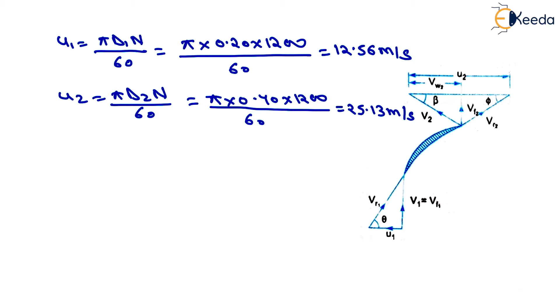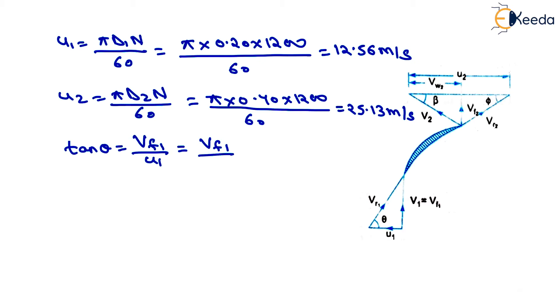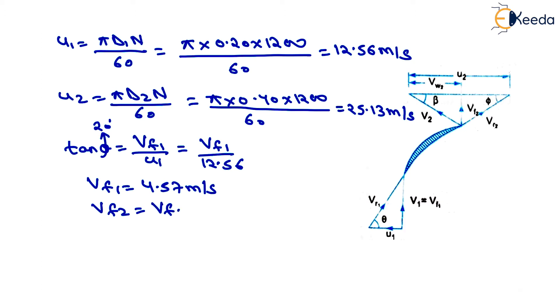From the inlet velocity triangle shown here, tan(theta) equals vf1 divided by u1, that is perpendicular over base. We calculate vf1 using tan(theta) equals vf1 over u1, where u1 is 12.56 and theta is 20 degrees. After solving, vf1 equals 4.57 meters per second. Since vf1 equals vf2, vf2 is also 4.57 meters per second.